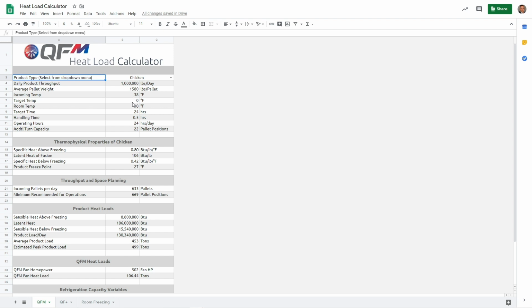Our incoming product temp is 38. Our target temp is 0. A room temp at -10 Fahrenheit. Target time or turn time of 24 hours. Handling time, we have this example at 0.5 hours. QFM is typically just a few seconds worth of handling. And then we look at operating hours per day. So we're going to be receiving, stocking, and retrieving 24 hours a day in this operation.